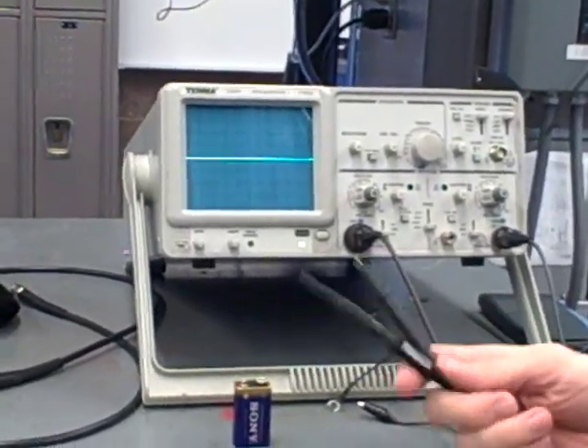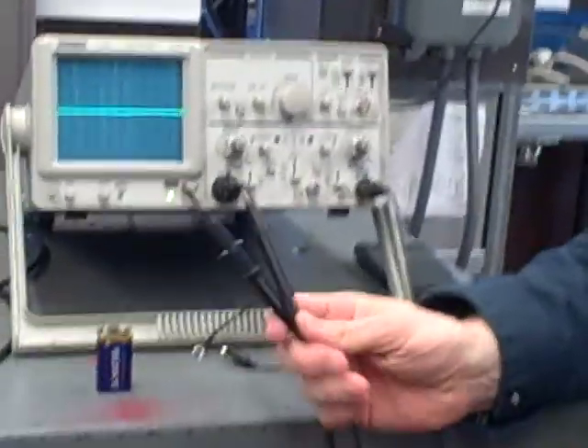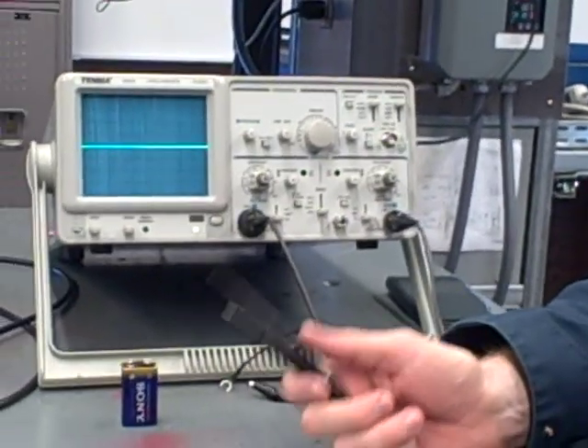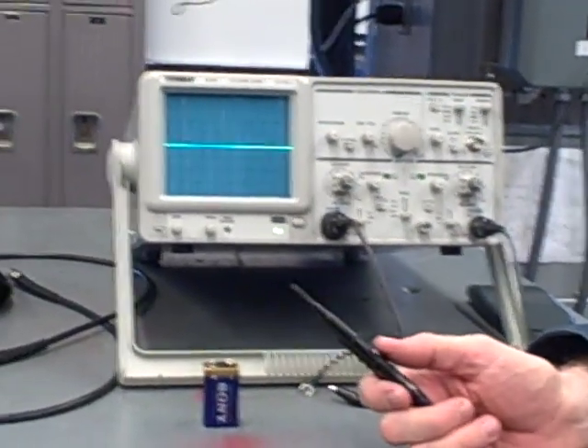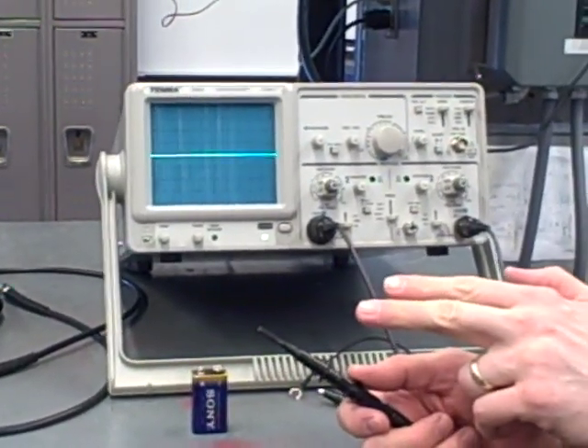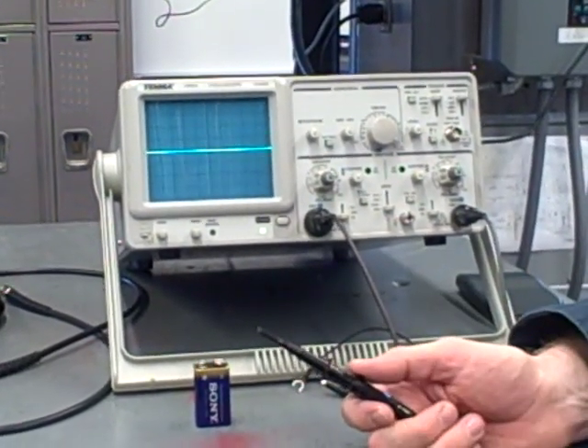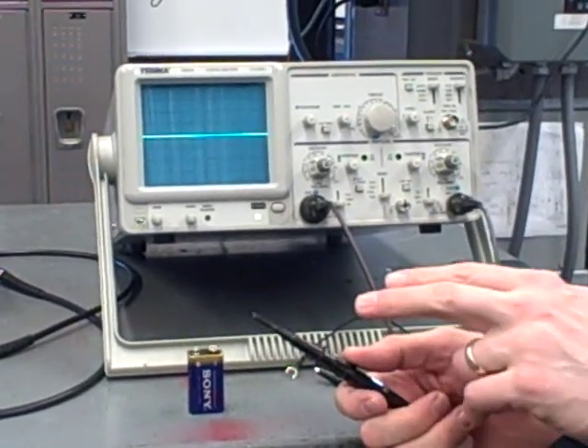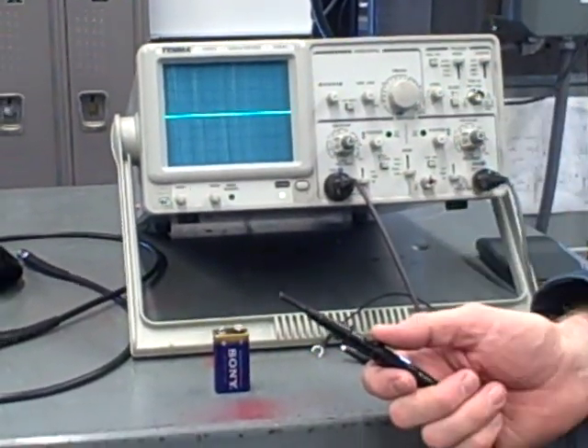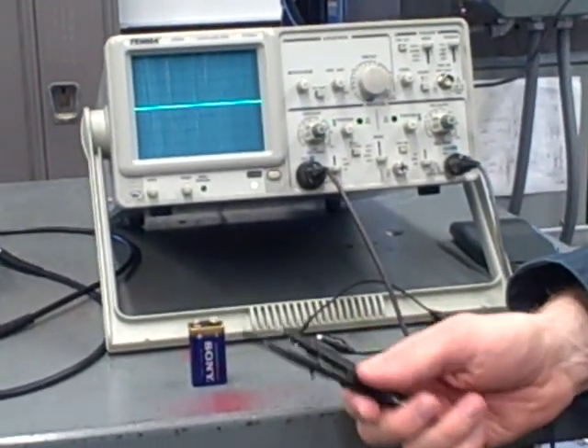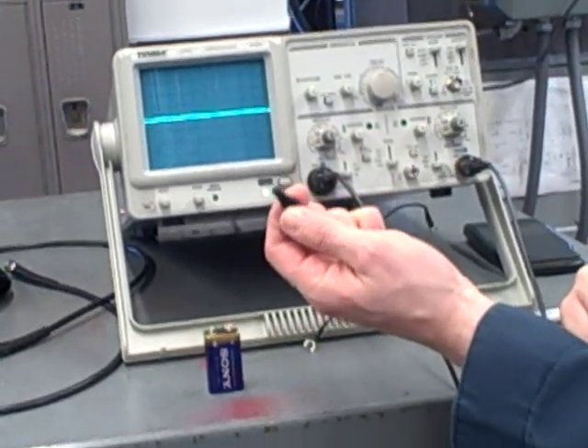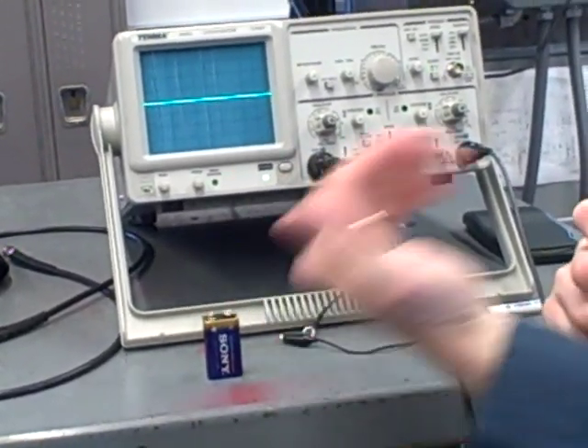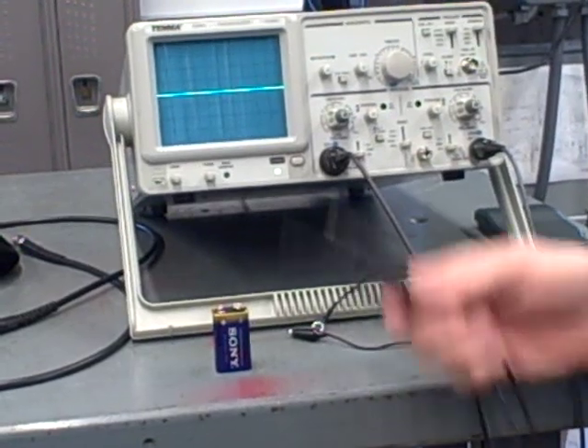This is not just useful in high power, dangerous circuits. This is also useful for things like communication networks. If you're looking at a communication network, a two-wire twisted pair, where neither of the wires is grounded, say for example RS-485 or RS-422, where it's a balanced, ungrounded differential signal pair, you do not want to forcibly ground one of those communications lines because you'll cause all kinds of signal reflection problems. So this is what you do.